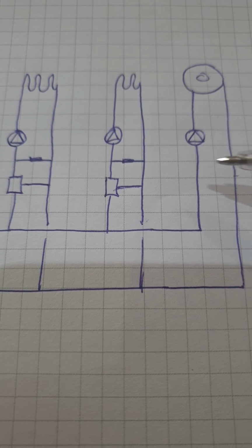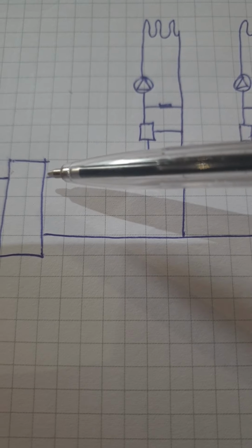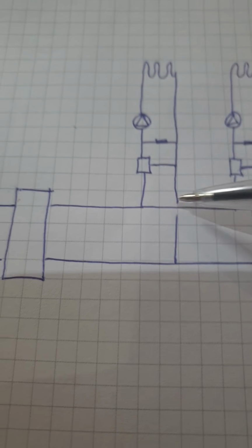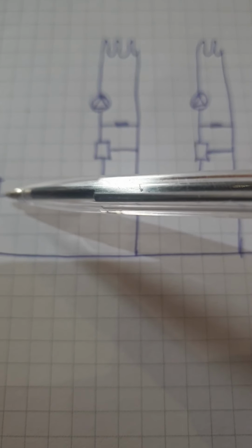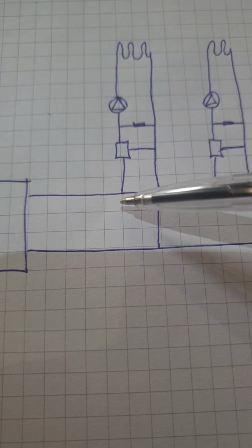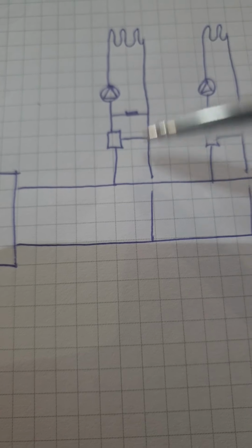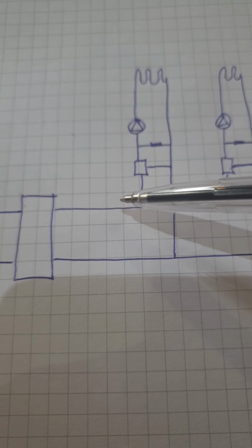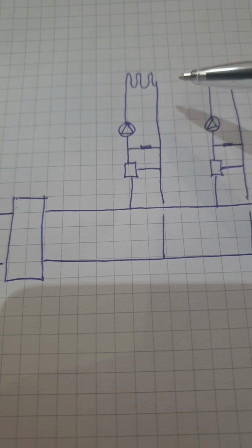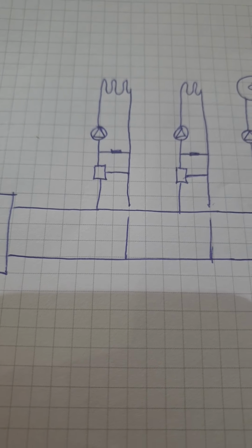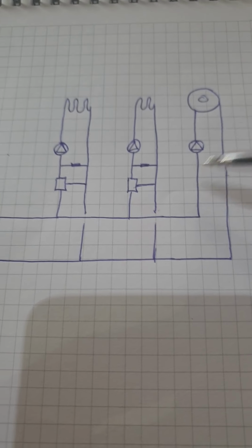You've got the option to have these multiple different control systems. The one thing you need to bear in mind with these systems when you're designing them is the size of pipework on the communal area. So on traditional high temperature underfloor heating systems, the pipes could be sized based on your delta T20 along the system because you're delivering high temperature water to the underfloor. But on a low temperature system, these pipeworks have to be designed to take the full flow rate of the underfloor heating system, which is normally designed on delta T7. So be very careful of that, not to undersize these pipes, especially on bigger systems.